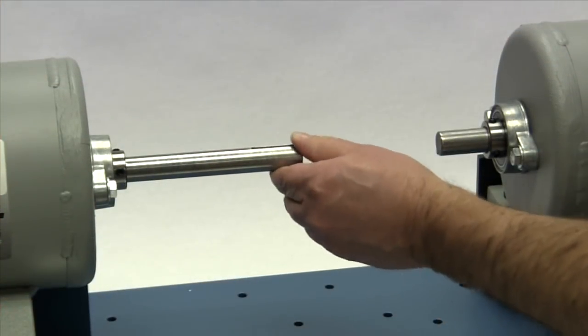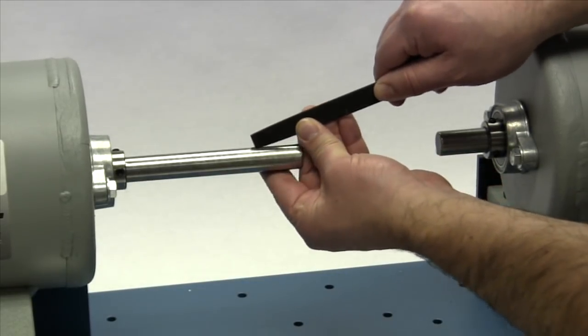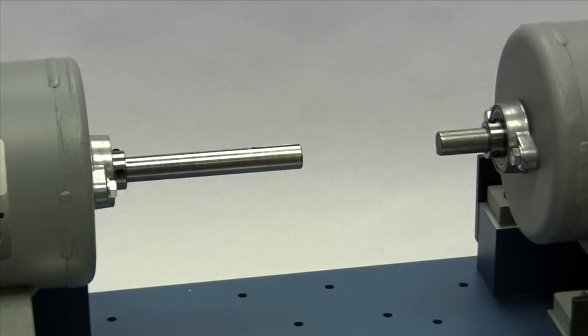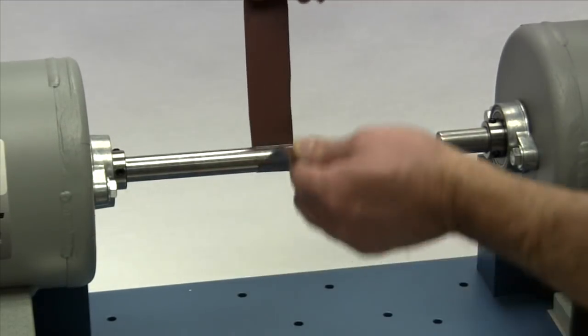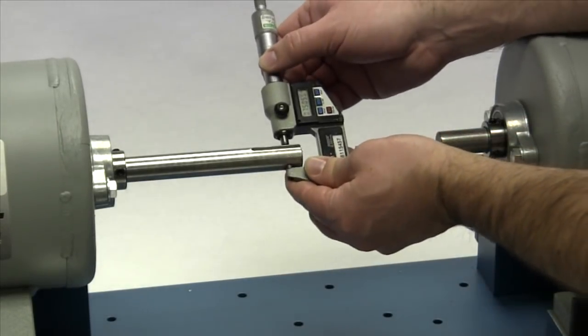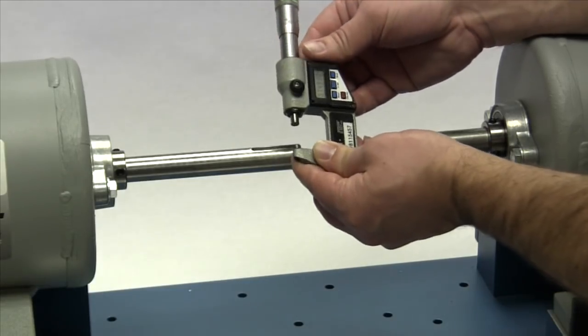It is important that you inspect the shaft and clean off any nicks or burrs from the keyway or shaft. A fine-toothed file can be used to clean burrs from the edge of the keyway or large dents in the shaft. The emery paper can be used to clear the shaft of any rust or fretting corrosion. This would be a good time to measure the shaft and ensure the shaft diameter matches the coupling bore size.